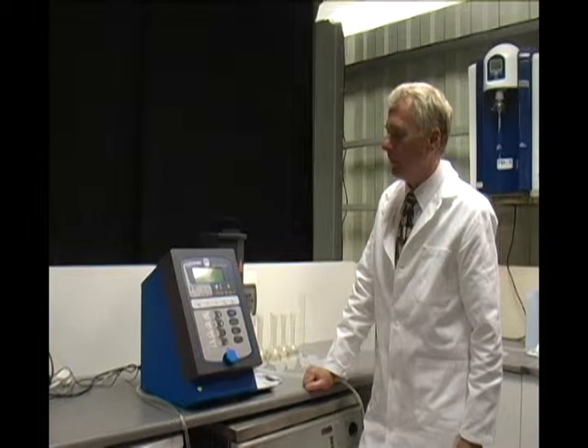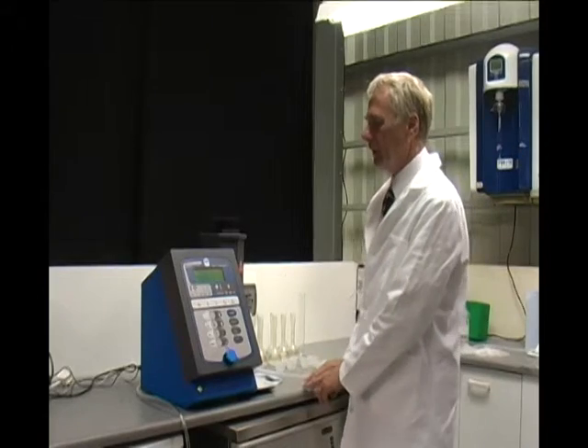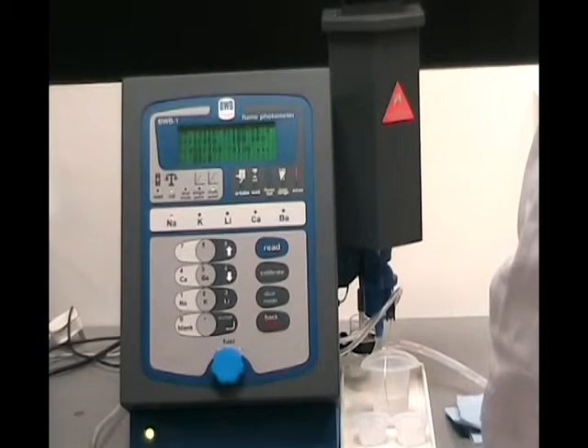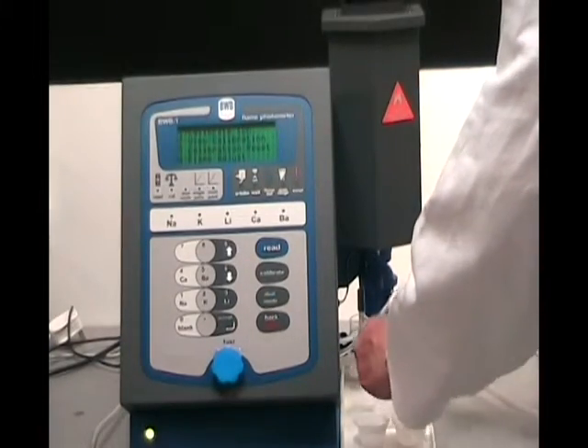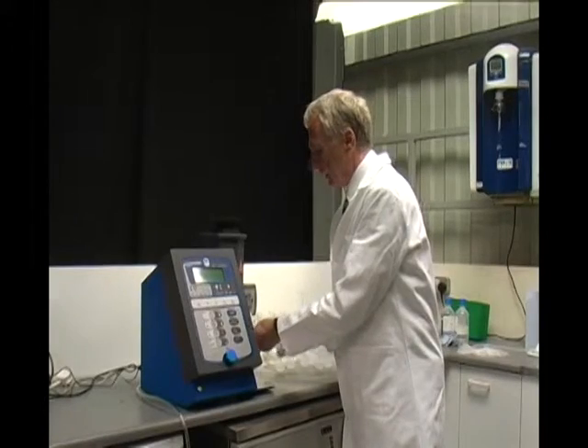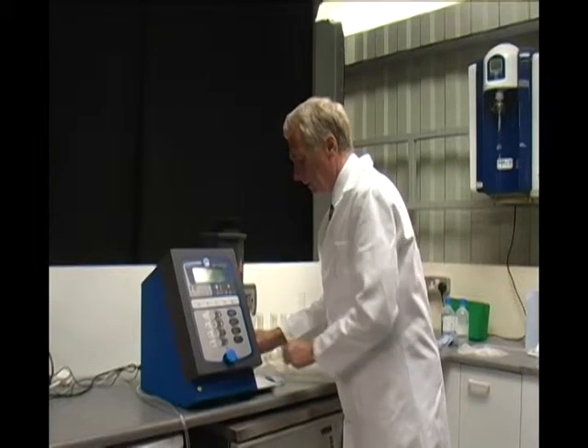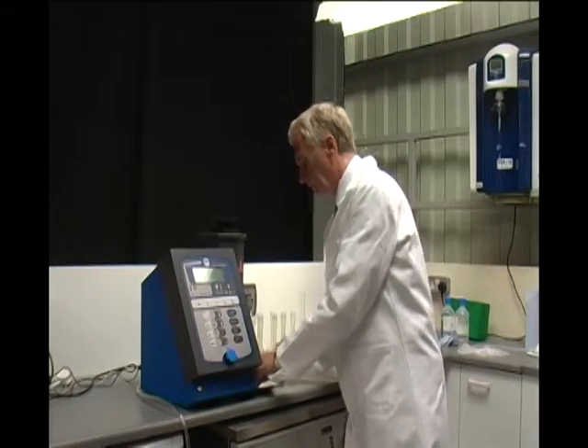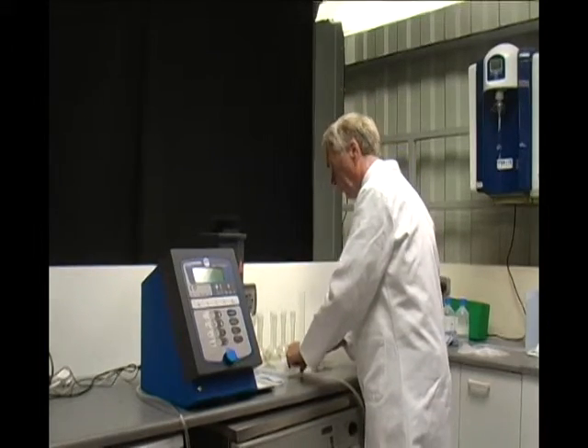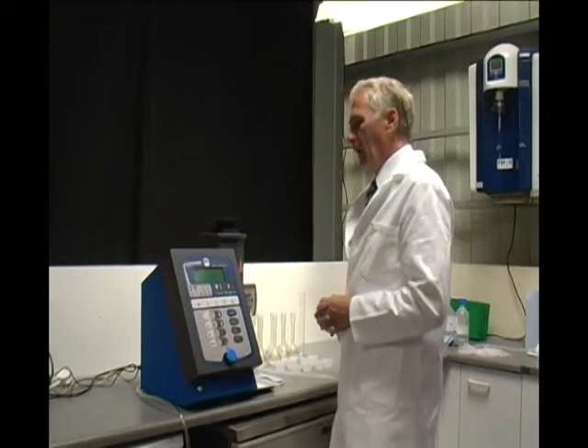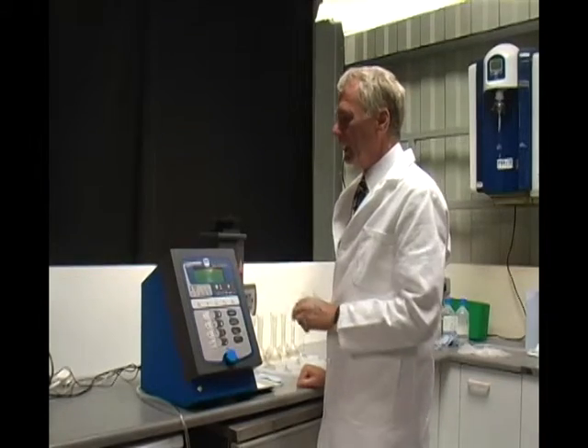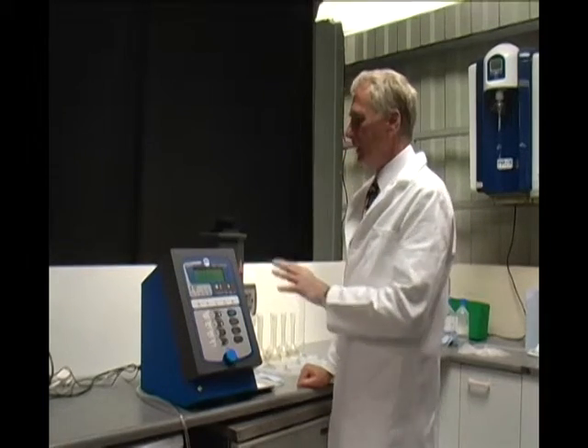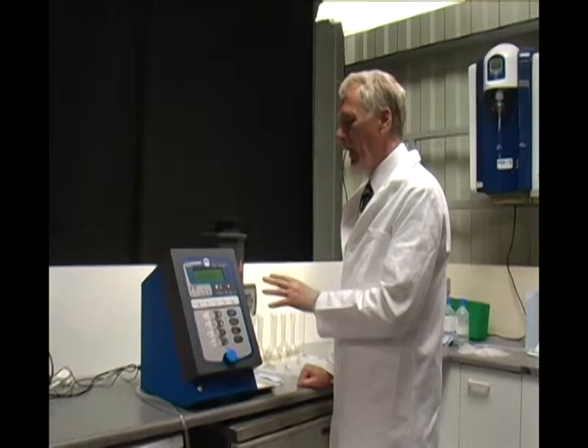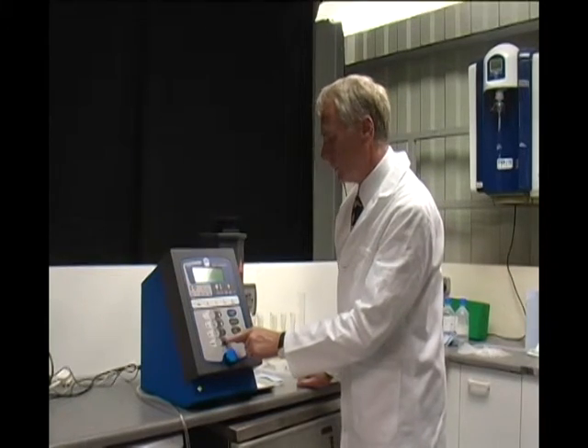It's now determined that the reading is stable and is taking the reading that it needs for calibration. So that's that calibration complete. I can now wipe the aspiration tube and put it back into DI water so that it will flush the chamber. At this point I could go and view the calibration that I've just done, but instead I'm going to continue and calibrate the other two ions that I want to do.